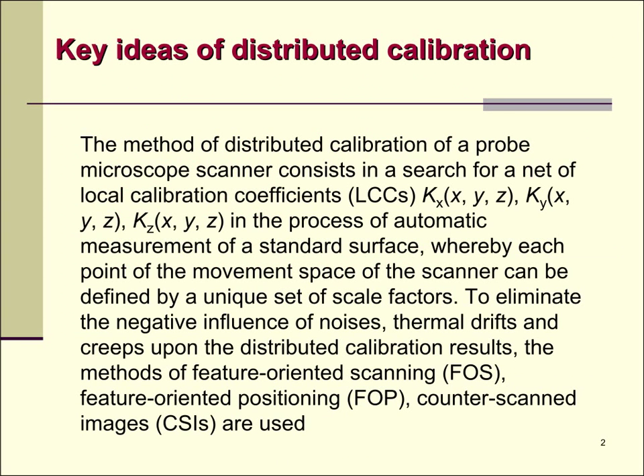The method of distributed calibration of a probe microscope scanner consists in a search for a net of local calibration coefficients in the process of automatic measurement of a standard surface, whereby each point of the movement space of the scanner can be defined by a unique set of scale factors. To eliminate the negative influence of noises, thermal drifts, and creeps upon the distributed calibration results, the methods of feature-oriented scanning, feature-oriented positioning, and counter-scanned images are used.